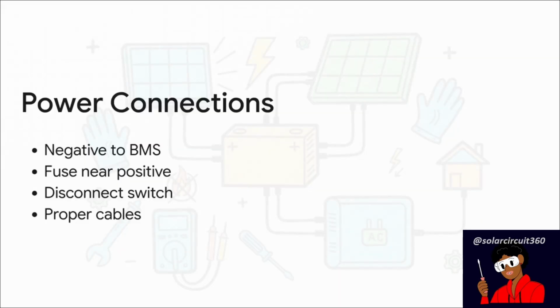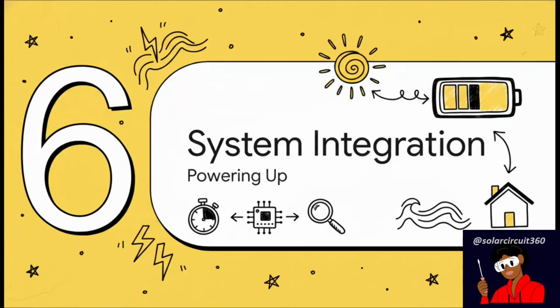And that is exactly why your essential power connections absolutely have to follow a strict engineered framework. First, your main negative must be routed through the BMS. Why? Because the BMS is the ultimate gatekeeper. It can physically cut the ground connection to stop the flow of electricity if things go south. Second, your main fuse has to sit right up near the battery's positive terminal so it can catch any downstream shorts immediately. Oh, and you definitely need a dedicated disconnect switch. Routing our power this way doesn't just massively improve your baseline safety, it makes your long-term maintenance so much easier. Which brings us to our final phase, Section 6, testing and system integration, powering up.